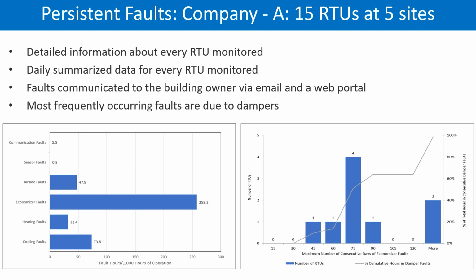When we dug deeper into these economizer faults, what we found is that these economizer faults were persistent. In the plot to the right, we see the number of consecutive days, 24 hours per day, of economizer fault for 9 out of the 15 RTUs. So what we learned is that there was a percentage or a group of, say, bad apples that were contributing and skewing this economizer fault frequency data.